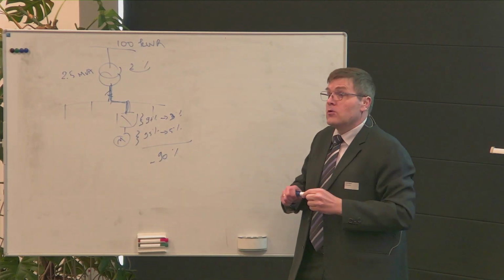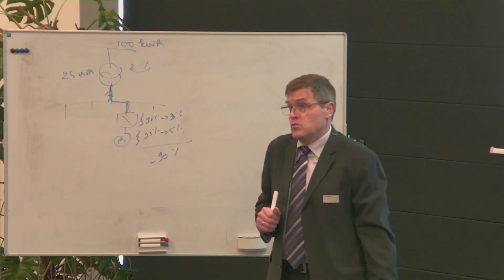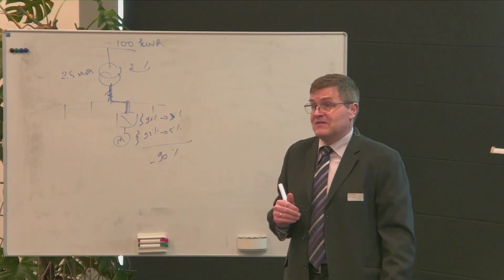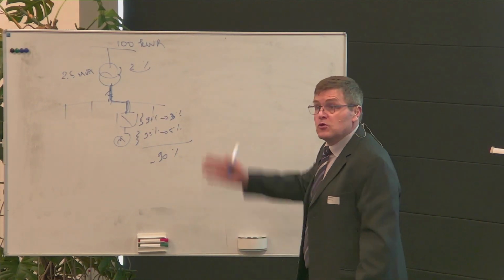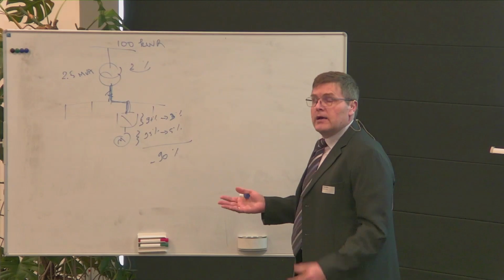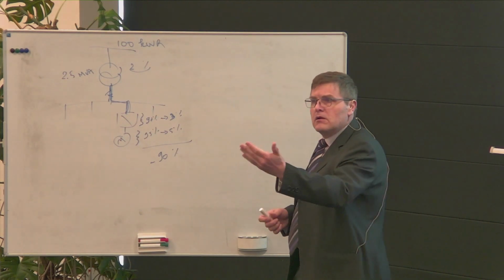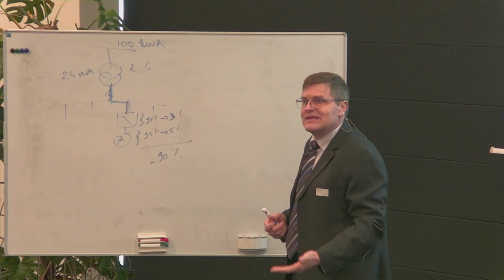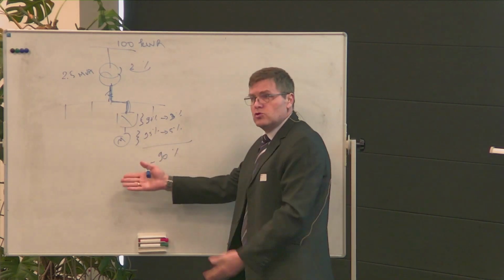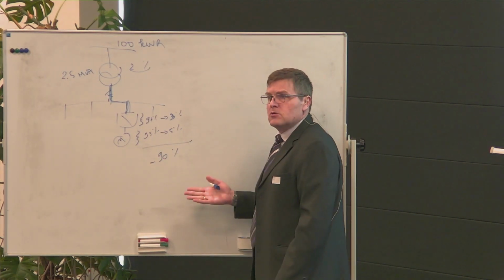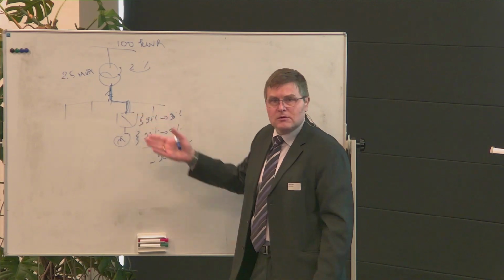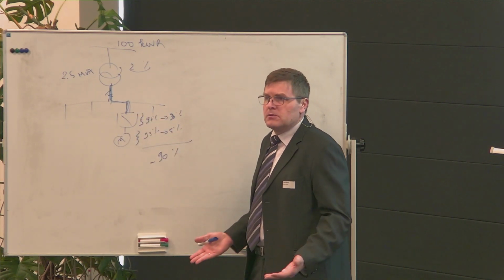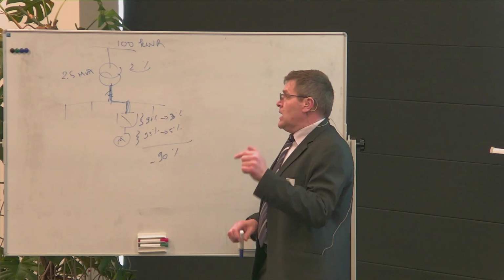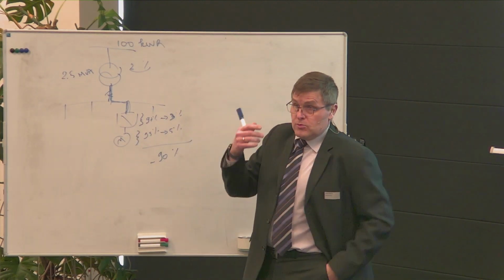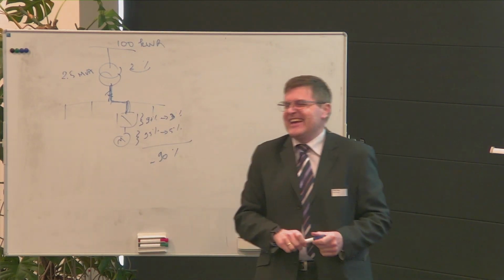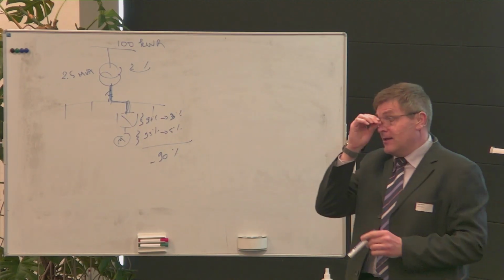So when people tell you that you are going to have 10% energy savings, that means that you have no losses anymore. You will increase your efficiency by 10%. That means that for the same production, you have no losses at all. So no losses in the transformer, no losses anywhere. That's simply not possible. So here, the customer with dollars in his eyes said, okay, I need an active filter just to make a test.